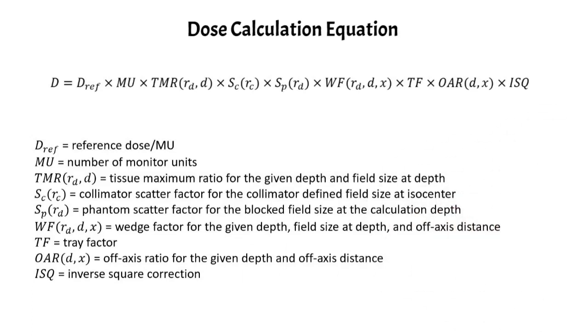I'm just going to pop up some of the definitions here. DREF is your reference dose per monitor unit established during linac calibration. MU is your number of monitor units. TMR is the tissue maximum ratio for the given depth and the field size at depth.